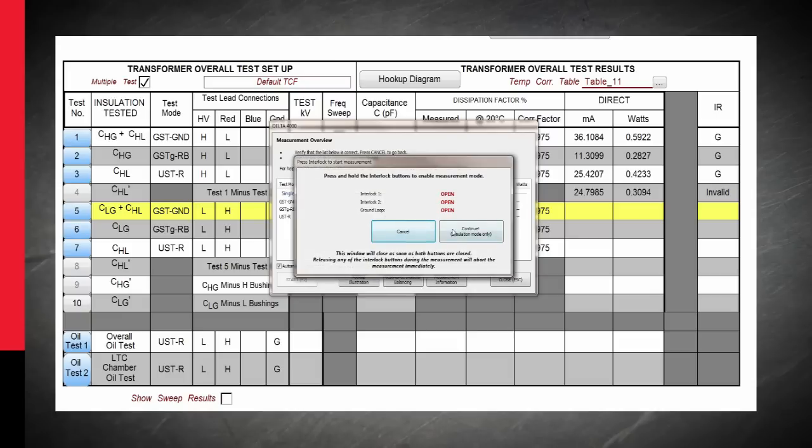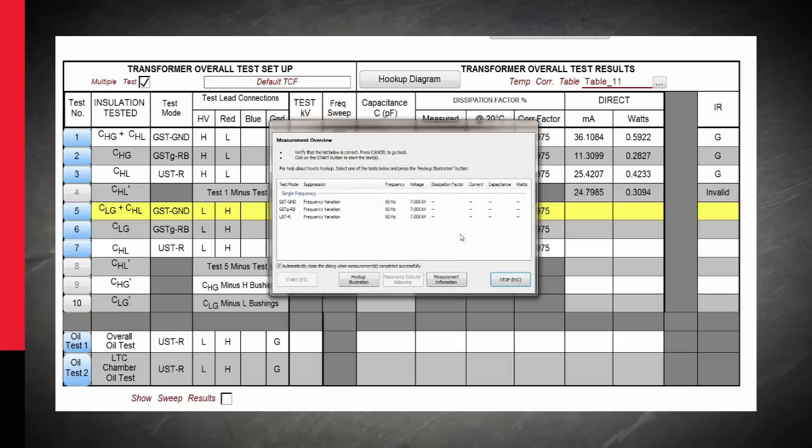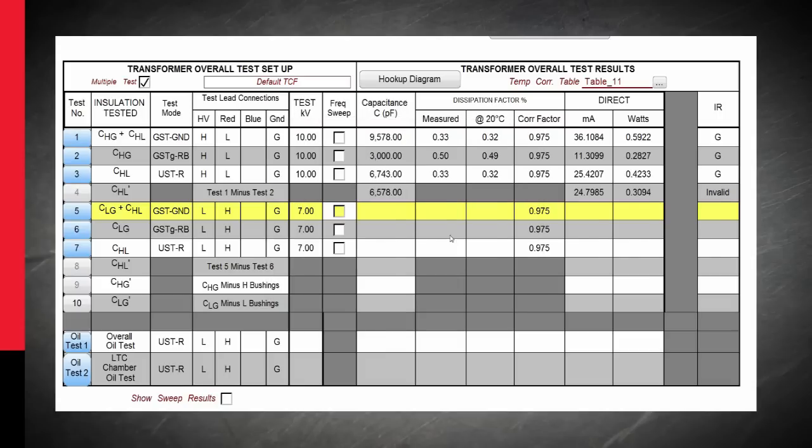Once prompted, we close interlocks at appropriate time and test voltage is once again applied to transformer. We can observe the results as they are completed on the dialog box. Once we see the results are as expected, we can confirm good insulation condition of the main body of the transformer.